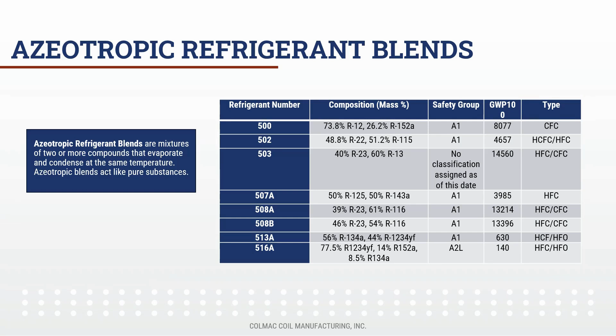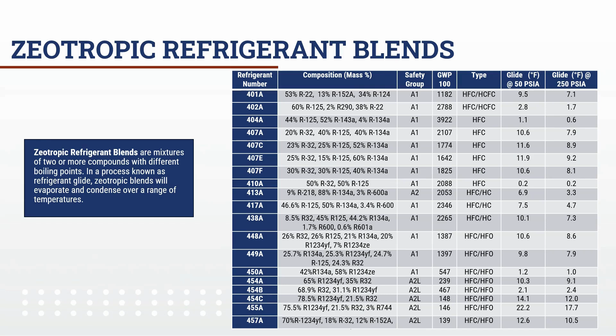Zeotropic refrigerant blends are mixtures of two or more compounds with different boiling points. In a process known as refrigerant glide, zeotropic blends will evaporate and condense over a range of temperatures. Therefore, this chart also lists glide for each of these refrigerants at both low and high pressure conditions.